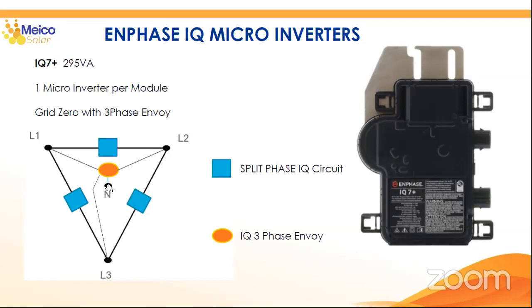So you have to build three microinverter circuits. The amount of micros per circuit isn't important; what matters is that the circuits are balanced, meaning the number of microinverters per circuit is the same, so you have the same power in each circuit. You put the first circuit of microinverters between line 1 and 2, the second between line 1 and 3, and the third between line 3 and line 2, as you can see here.